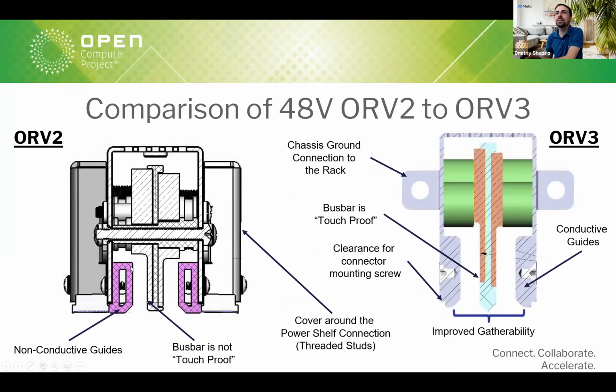The guides we had on the outside for ORV2 were non-conductive, so they pretty much just acted as guides. Whereas the guides on ORV3 are actually conductive, and they provide grounding from the chassis to the bus bar, and then further onto the rack.